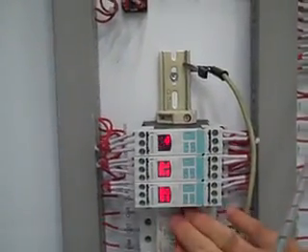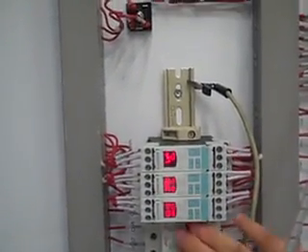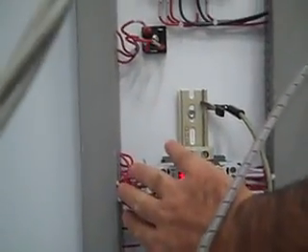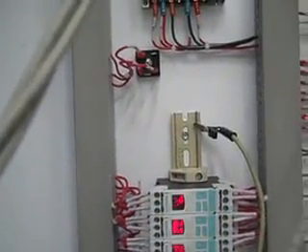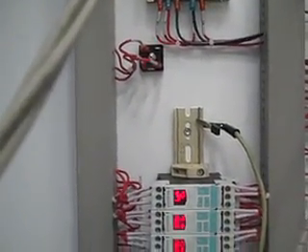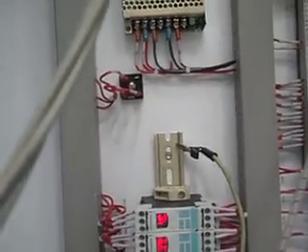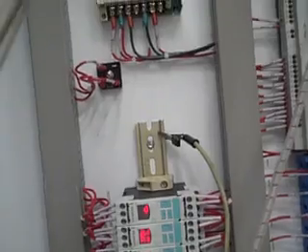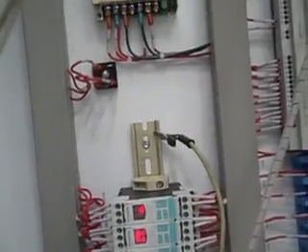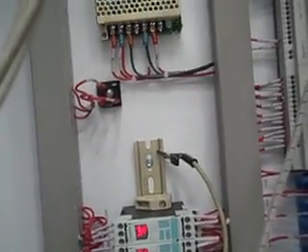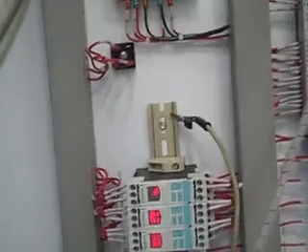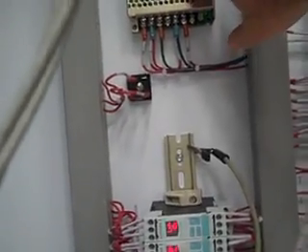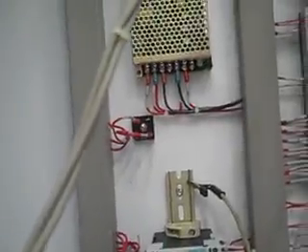These are the circuit breakers that protect the sensing for the relay. There's 480 volts coming into the top of the relay, and you also provide the power for the controls, these control relays here that feed the transfer switches and send a start signal to the generator, making the switch flip to whichever side. This is a power supply that keeps the 24 volts stable for the PLC.